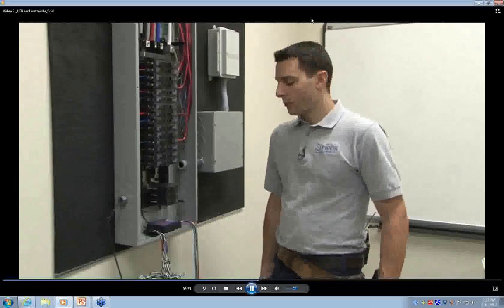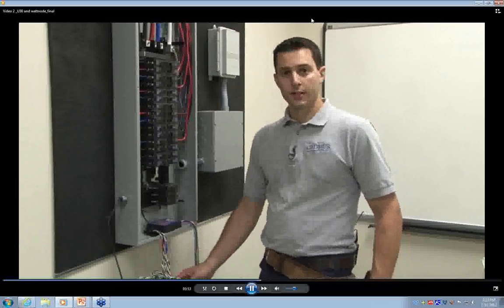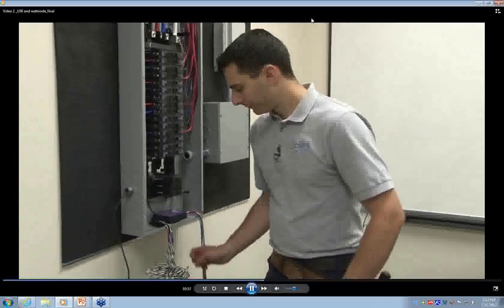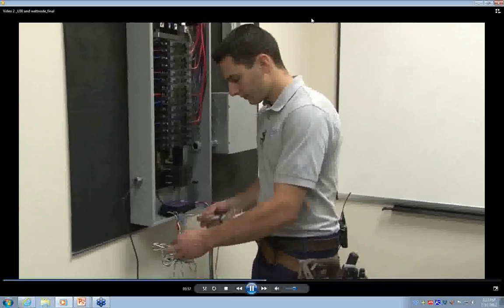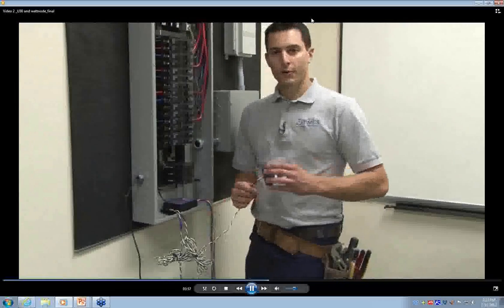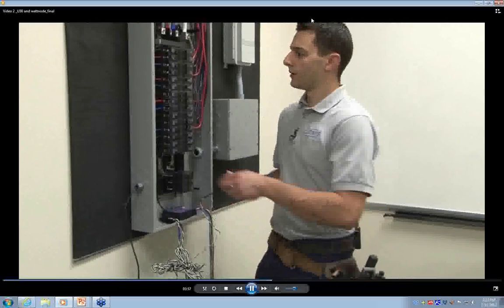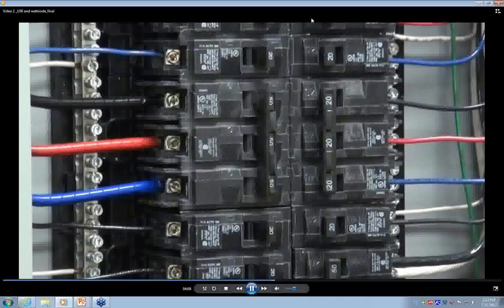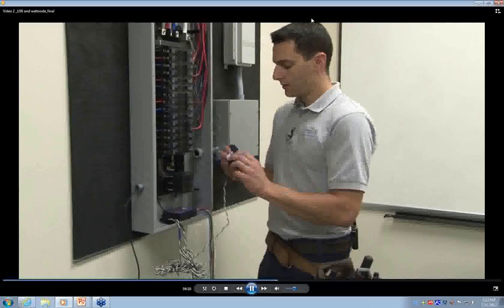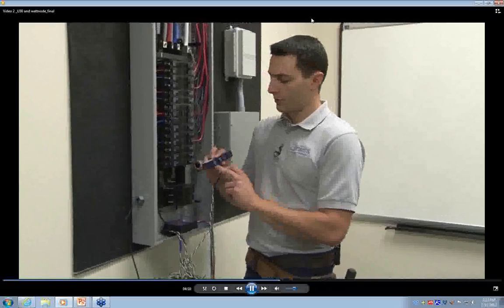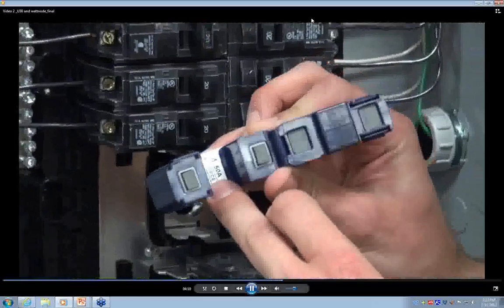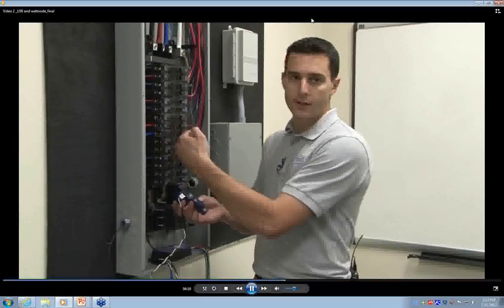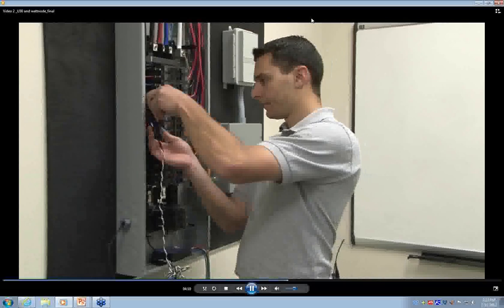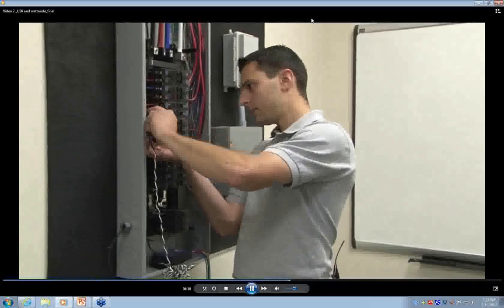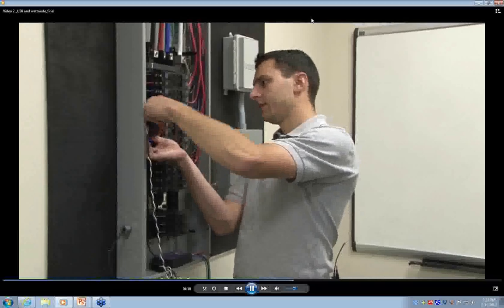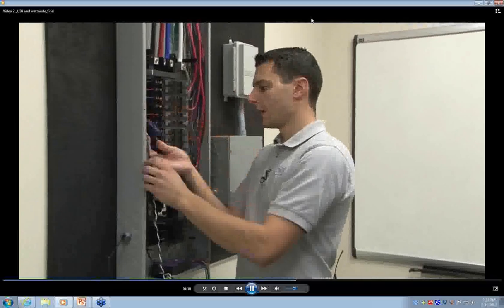Now that everything is wired to the watt node, we can begin connecting our CTs to the phase conductors. We will start with the black phase A CT. This will go around the black conductor on our circuit. Once again, this particular CT is directional, so we want to make sure the arrow faces the source, or in this case, faces the center of the panel board. And this CT just clips shut to know we have a secure connection.